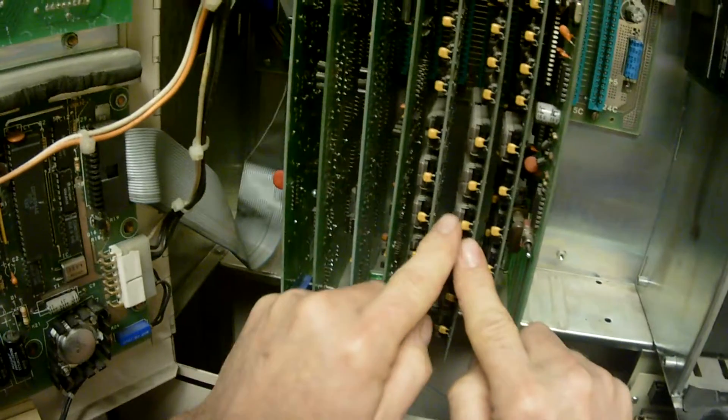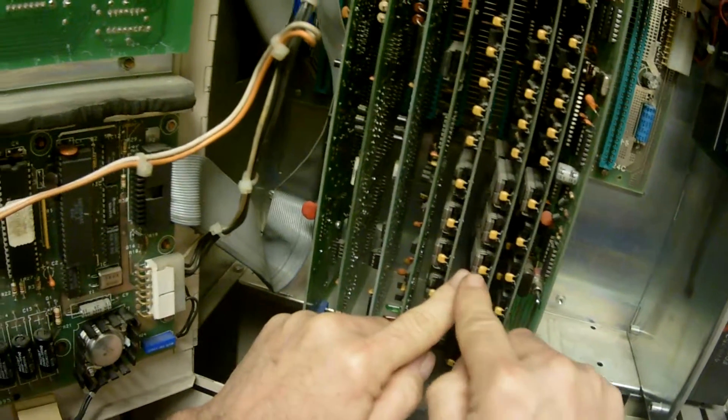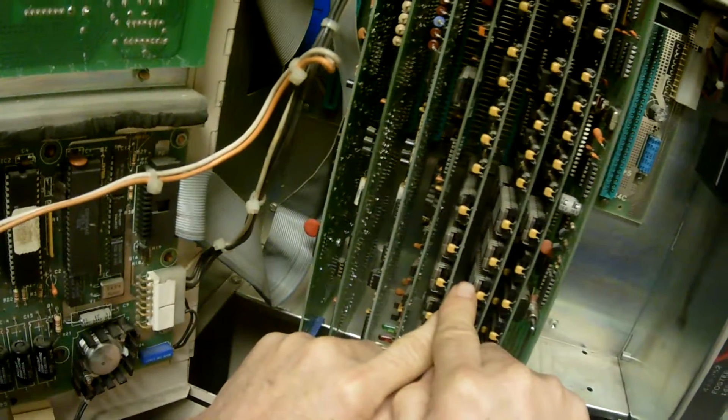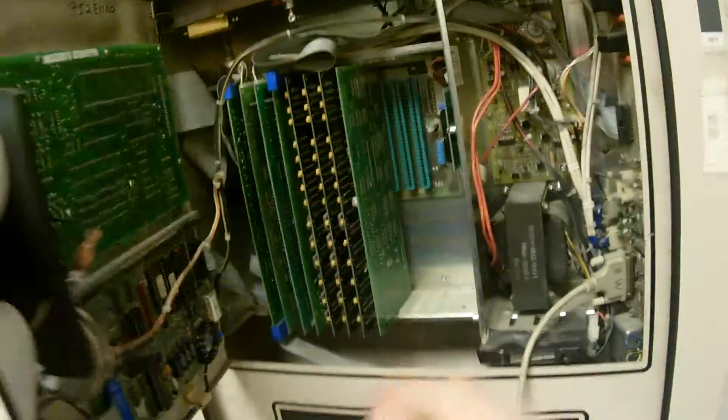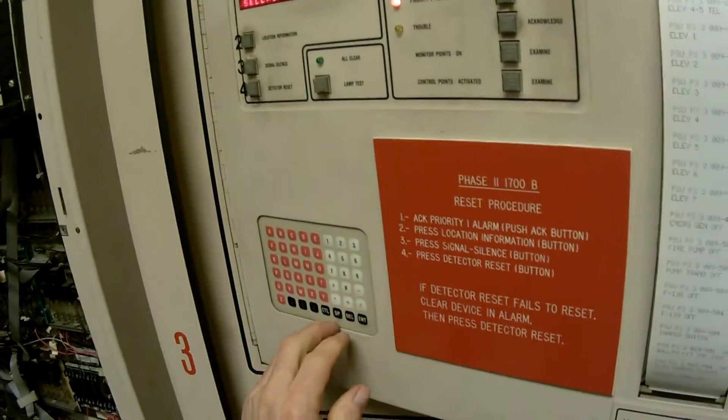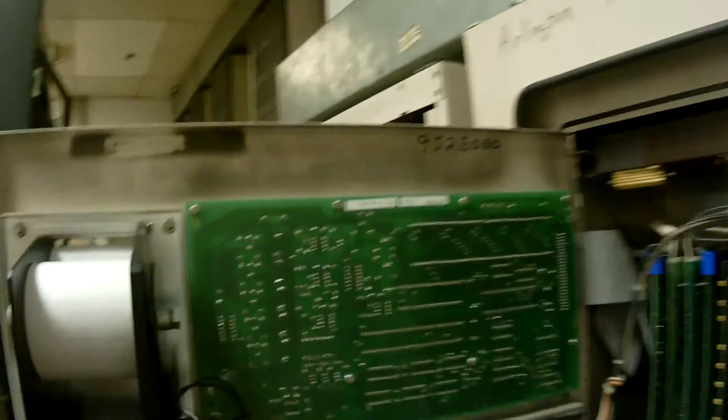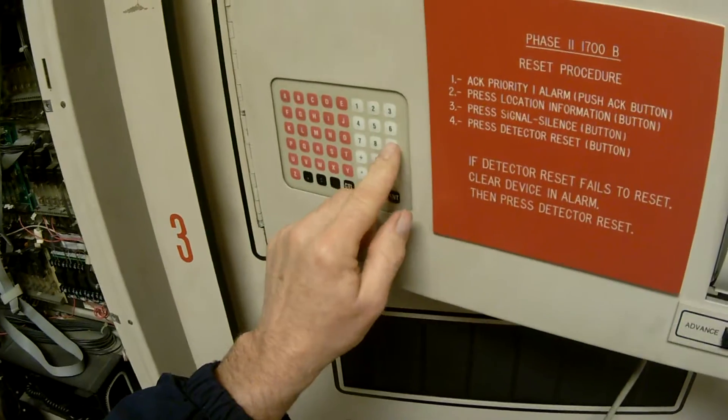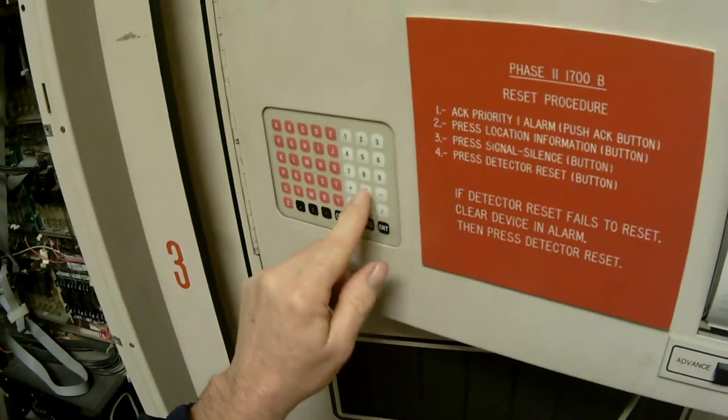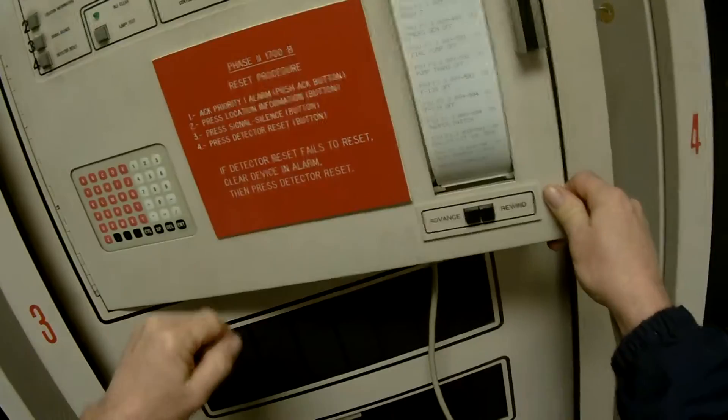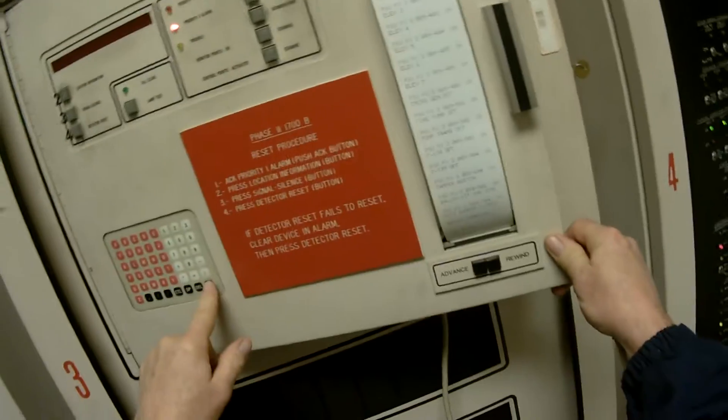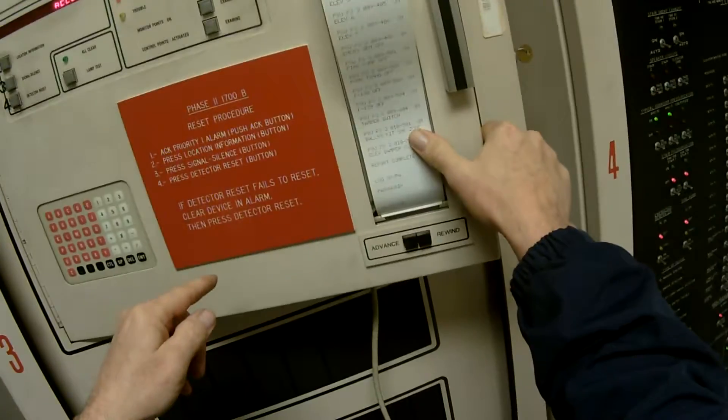The log on for this would be L-O-G space O-N slash P-A for password. And you'll see that it says log on and it's looking for a password. Now, written inside the door is our password here. Another way to find a password is to actually go in and look at the PROM chips. The password is written on the label on the PROM chips, but sometimes they used to take and scramble, take the first letter off the beginning and put it in the middle and scramble it up a little bit. But I like to write it down so I can see it all the time. 952E 080. If you notice, nothing printed out because I don't want you to see what the password is. Enter, and it says accepted.